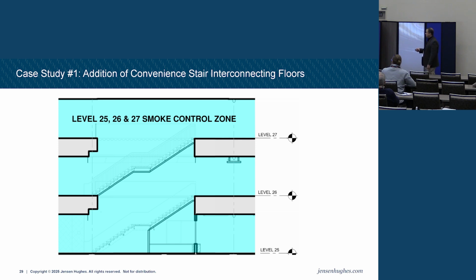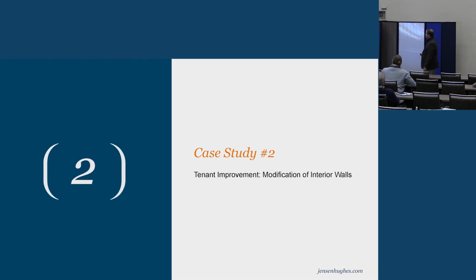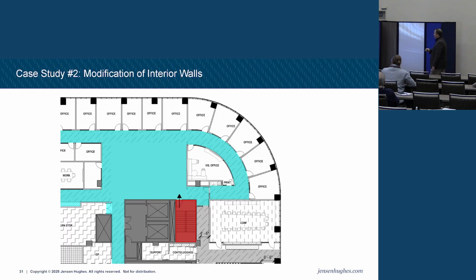So now none of that system works anymore, and your smoke can readily spread throughout floors, right? So there are ways to deal with this. We can enclose it differently. We can do detection differently. But it needs to be caught before the renovation occurs, right? And now your smoke zone just went from that to this. We can probably still work with it, but we need to know earlier in the design process. This one, interior walls, this is probably the most common. So this is my stair right here.